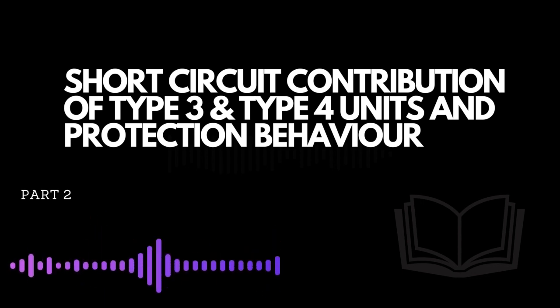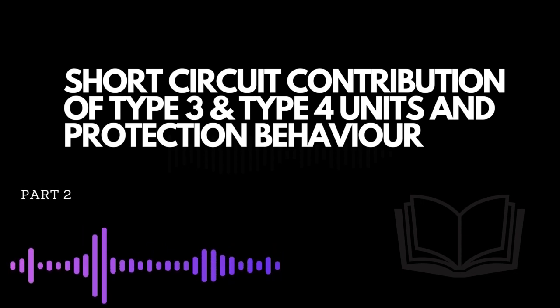Line differential characteristics follow two slopes. Slope 1 is applied for low restrained currents. In this case, errors in magnitude and phase due to the magnetizing current of current transformers are small, and the slope to restraint used is small.